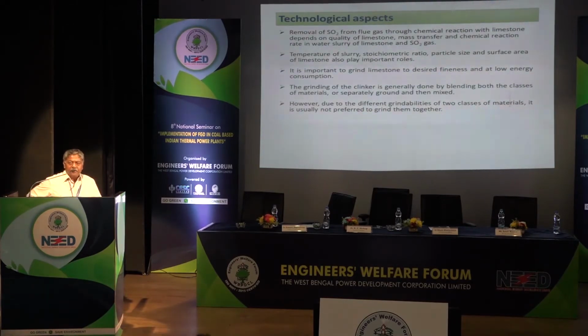All right. So this is a huge reduction ratio, from 75 millimeter to 0.045 millimeter. Now while we do that, it is desirable that the percentage mass of less than 10 to 15 micron will be minimum. That means for desulfurization purpose, the limestone particle size we require is broadly in the range of 15 to 40 to 45 micron.